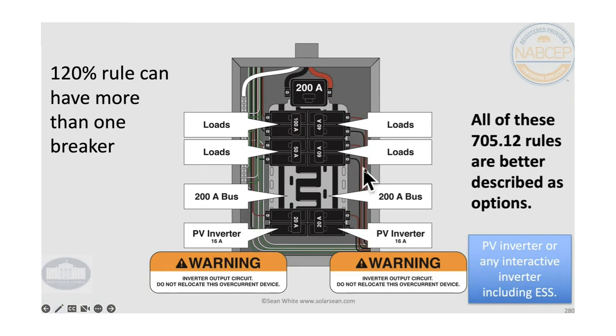And another thing about the 120% rule, where sometimes I think the wording needs to improve, even in the 2023 NEC, is that you can have multiple breakers at the opposite end. If there were 4 backfeed breakers, then you would put all 4 at the opposite end from the main breaker. It doesn't have to be one breaker. Some people read the wording and it's kind of confusing. It almost sounds like it needs to be one breaker and you would have to put in a subpanel, but that's not the case. That's not the intention.